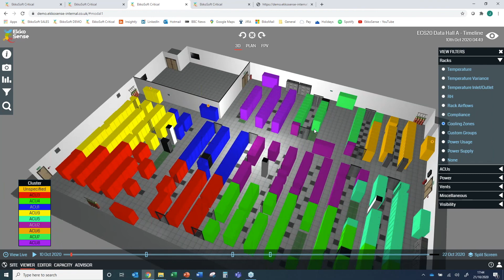So the first part is that the software is constantly learning. I'm just going to show you these cooling zones. As I zoom in, what the software is doing is constantly learning the cooling performance and linking it to your rack performance. So the software starts to learn how effective cooling units are being in the rooms and their effective zone of influence. This visual is showing you the software is learning through live and historical data that all these racks colored in red are predominantly cooled by this CRAC unit, the red CRAC unit, ones in yellow by the yellow unit, blue by the blue unit, etc., etc.